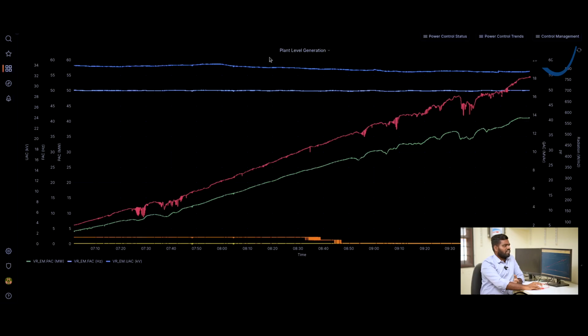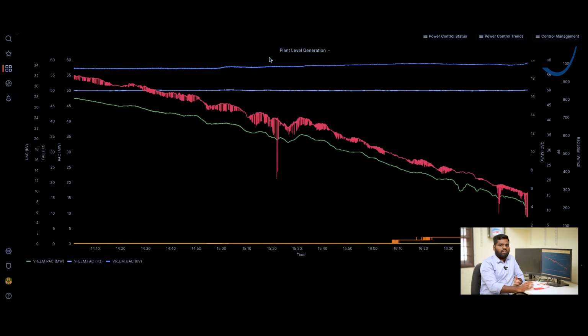And this is the trend screen. In the trend screen, there are plant generation trends, block wise trends, and feeder wise trends. In plant generation trends, we can check the overall plant active power, reactive power, voltage, and frequency. On the left axis we can compare overall active power, frequency, and voltage. On the right axis we have the overall plant reactive power, power factor, and radiation. Those are the plant generation trends.